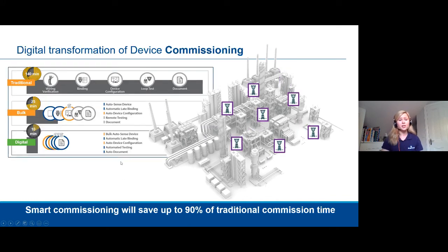But what about commissioning? Well, traditionally, commissioning was done with a field communicator and walkie-talkies, extremely time-consuming. So a better way to do this is with bulk configuration, where you have instruments wired and configured in bulk. Better, but not perfect, with AMS Device Manager alongside.